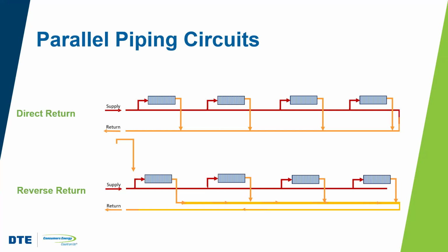Now, in these systems, there's a common supply and a common return, and you can see here that with the direct return, the hot water comes into the first emitter and then immediately comes back to that return line and goes back to the boiler. And then you've got water coming to the second emitter here, and then coming back immediately to the boiler. So the nice thing about the parallel system is that each emitter gets the same water temperature, so they tend to be smaller. But you have some issues with balance.